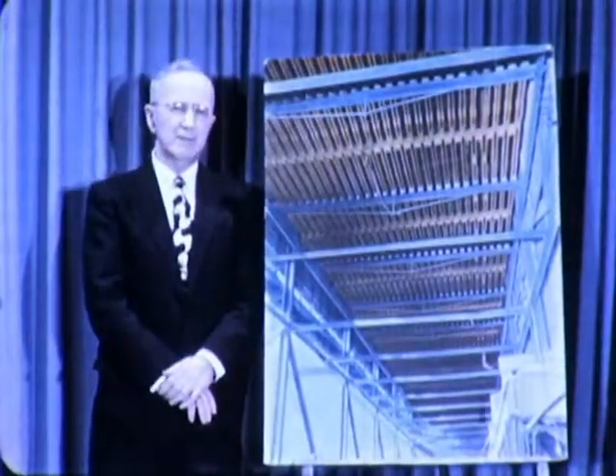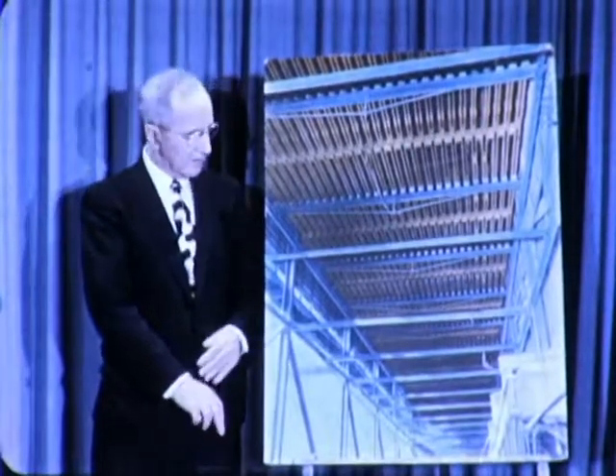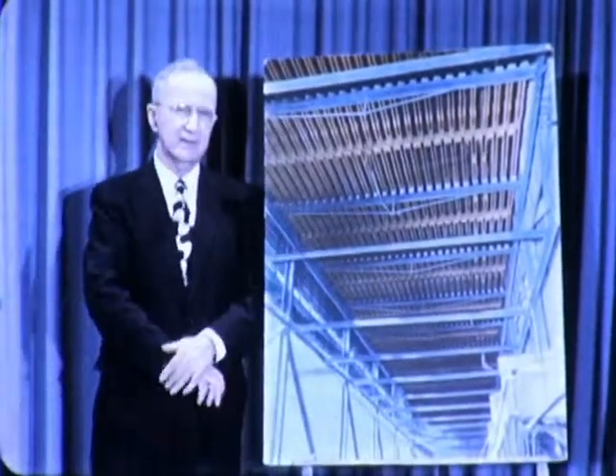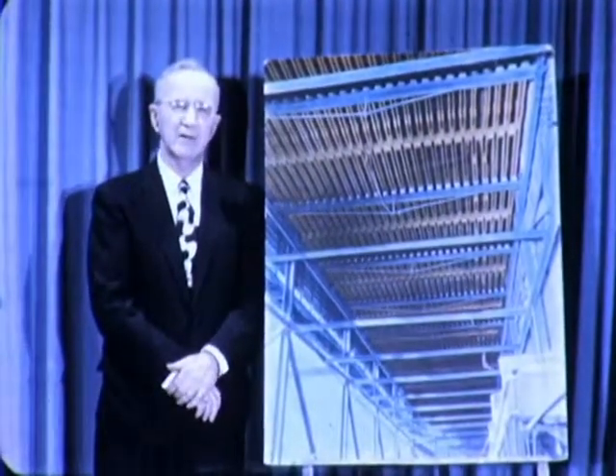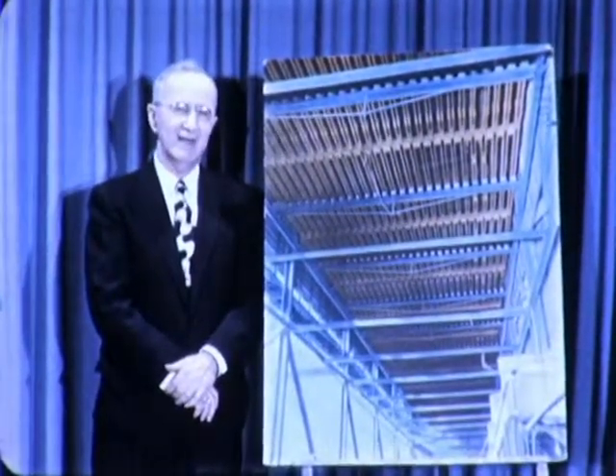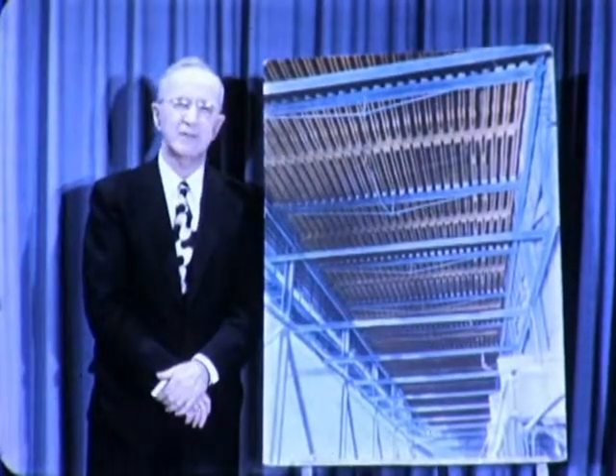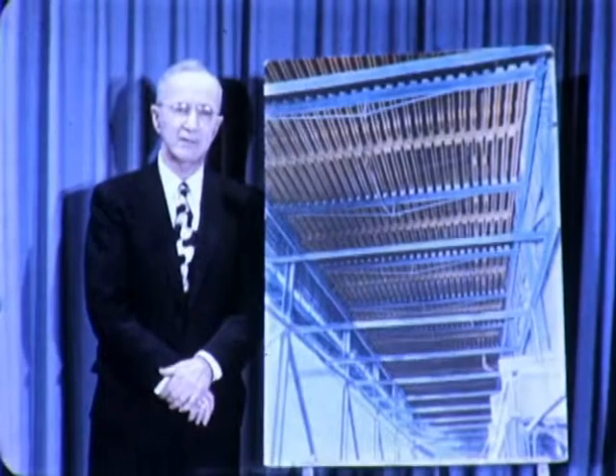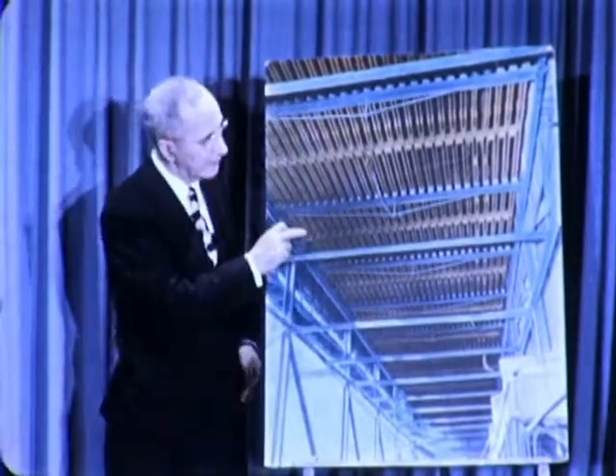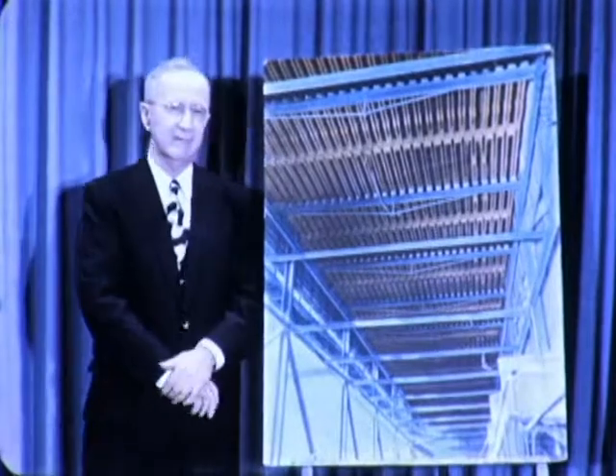This is a normal current. This is a short circuit current, and these are the mechanical stresses that can be developed. It's not like steam. It's not like water. You can't really visualize them. These stresses are invisible. When this system was originally installed, only 3 individual buses were required to carry the load. However, as time went on, additional capacity was required, so more buses were added, bringing the total up to 27.